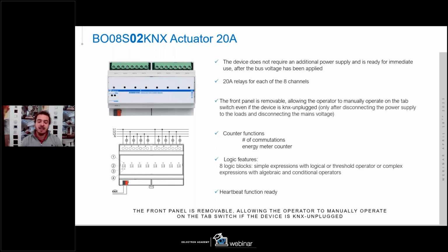Inside our device, you will find all the ETS parameters and functions that you already know about the single relay management. But in this case, we also add some new features, like 8 logic blocks to have the opportunity to enable logics and customize your project as you wish to fulfill any requirement from the end user. And we also add the heartbeat function on the device. This function permits the device itself to say to the KNX bus that this device is online by sending cyclically an on or a toggle command on the KNX bus.